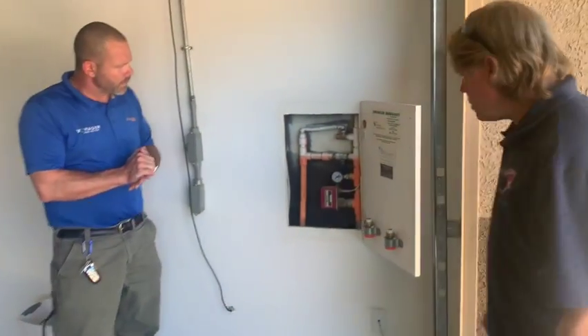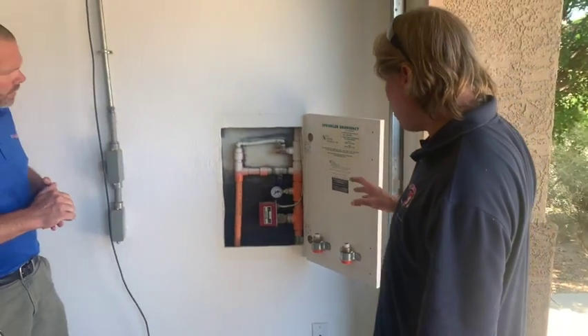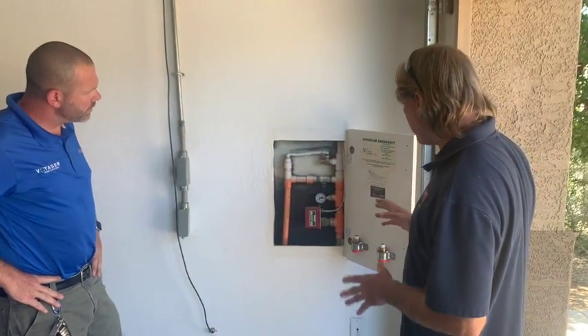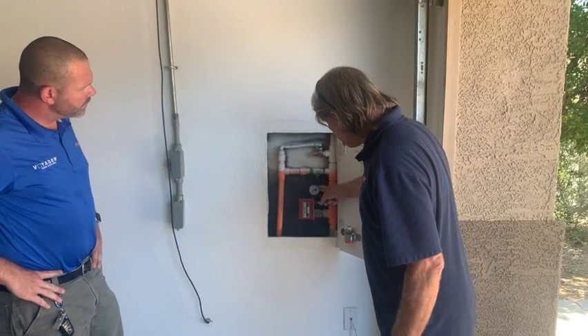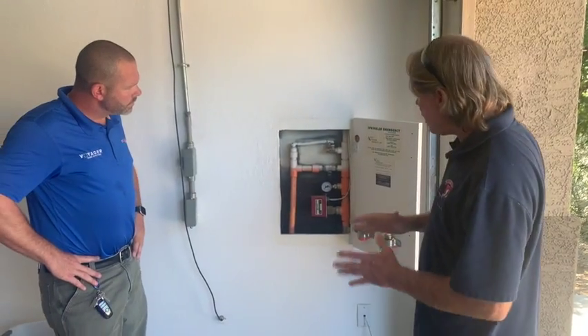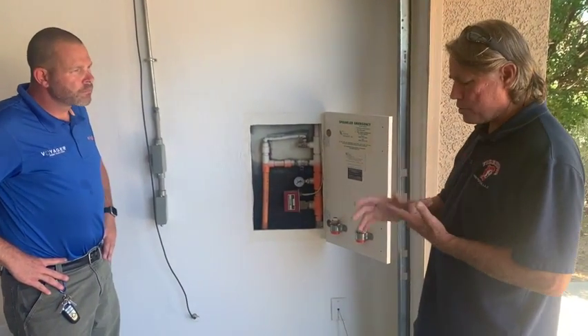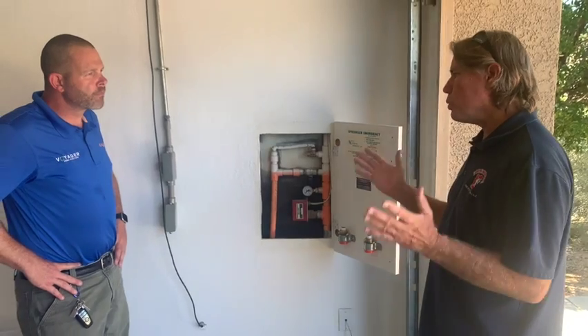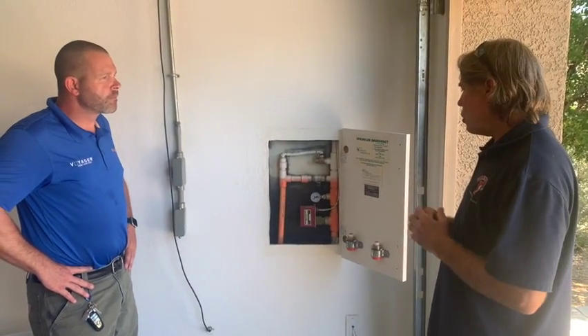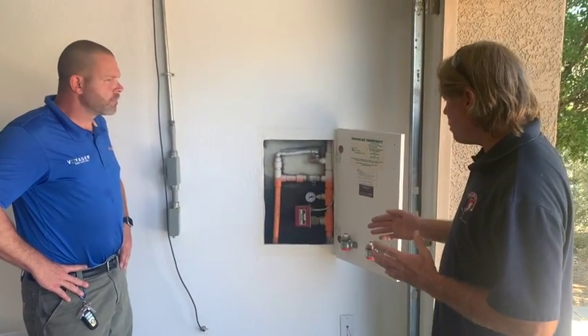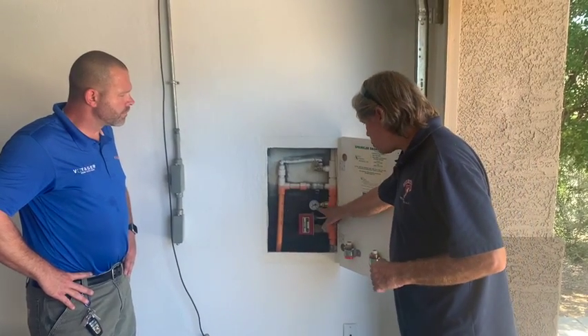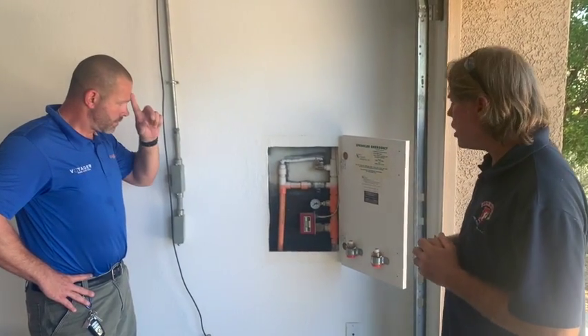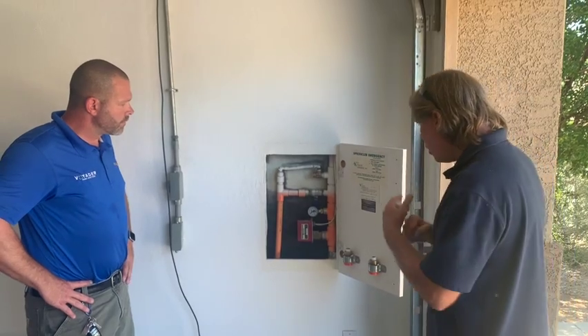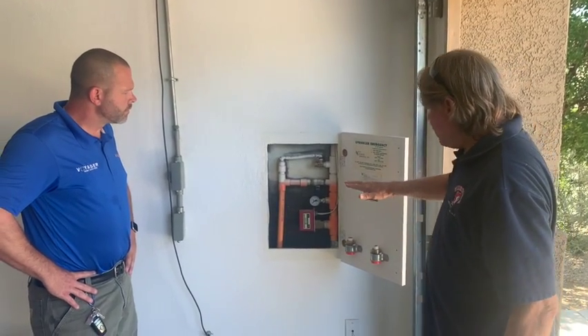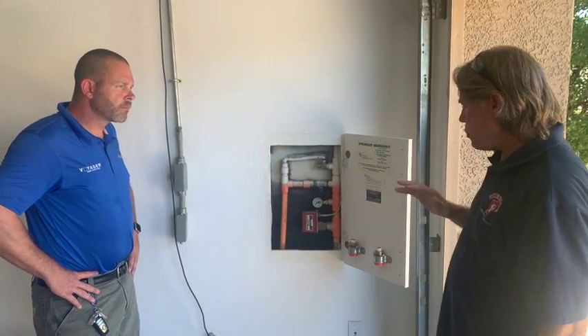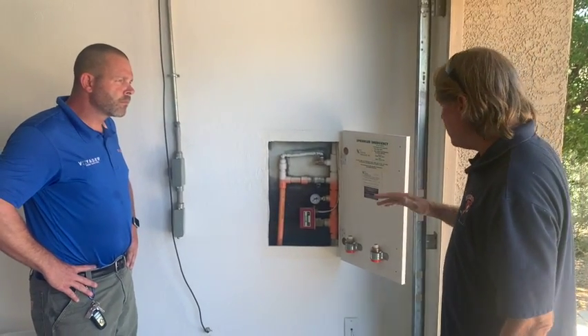When I came to this system to determine what was correct or incorrect, the gauge was the very first thing that needed changing. No gauge in the country, whether residential or commercial, should be more than 5 years old. So to meet that code, I changed that gauge, and I also put the date that we changed it, which was August of this year. In 5 years, for sure, we want to make sure that gauge gets changed again.